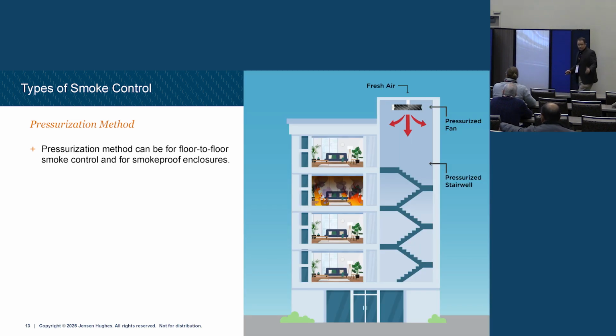So, pressurization method, we've talked about this a little bit, right? So I've got my stairwell here, I've got a fire here. Smoke detection goes off, or we get a sprinkler flow. Automatically, I turn on my fresh air source at the top. I say top, it's not always at the top, but we turn on that air source and we positively pressurize that stairwell. And when I say pressurize, we literally build a differential pressure between this stairwell and this building. And we have to measure that during commissioning.